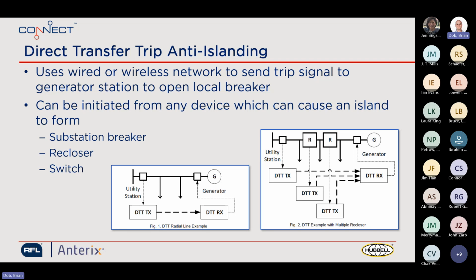It also could be initiated from other devices like a recloser. So if a recloser operates and locks out, that recloser can also be a source of islanding, so that can send a transfer trip signal to the generator as well. And we're showing that here in the bottom right image, where you may have multiple devices, multiple reclosers, a utility breaker that is being used to initiate a transfer trip signal to be received by the DTT receiver at the generator.